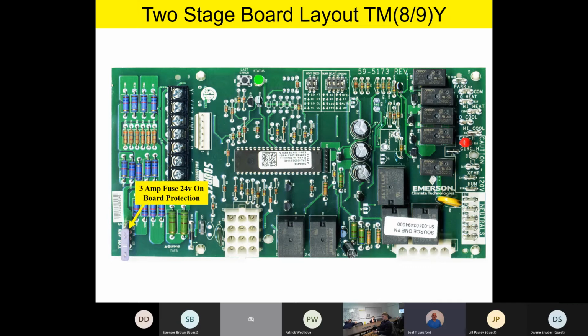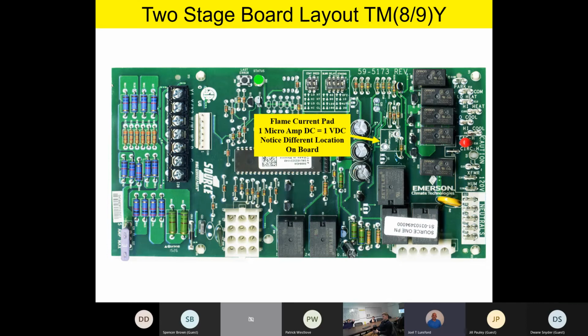To the left of that, you're going to find a 3-amp fuse for onboard 24-volt protection. So all of our 24-volt components on the board will be protected by that fuse. If you look closely on the silk screen right next to it, it does say 5-amp maximum. We ship it with a 3-amp fuse, but you can go up to a 5-amp fuse if you had some reason to do that.